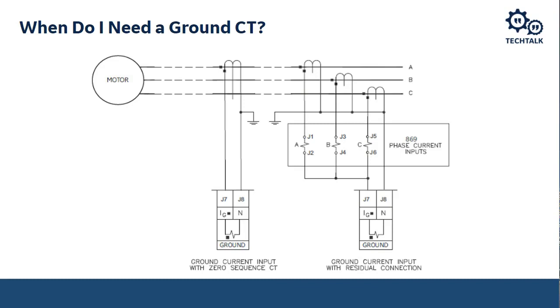The drawback of using this method is that the accuracy and sensitivity of my ground fault protection is only as good as my phase CTs. And what do I usually size my phase CTs for? I size them to detect phase faults, which are usually large fault currents. So they're usually sized higher, and because they're sized higher, especially with protection, the accuracy might not be there.